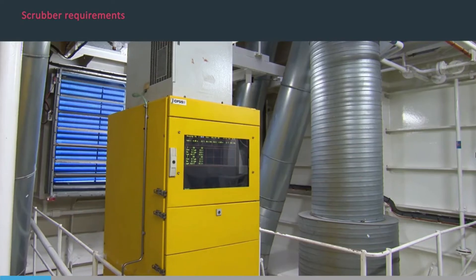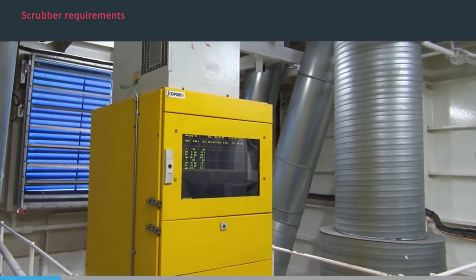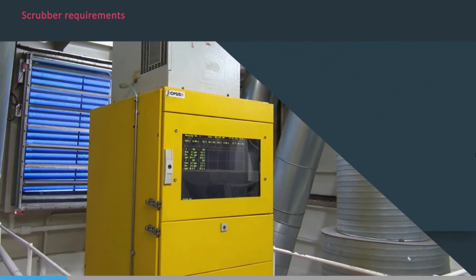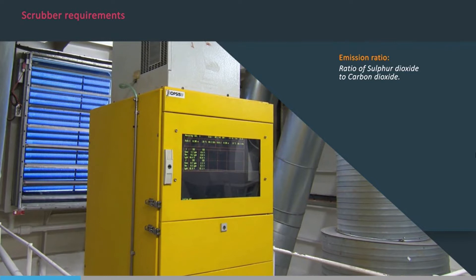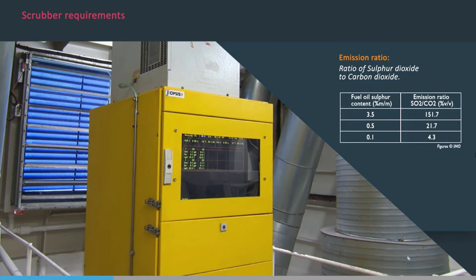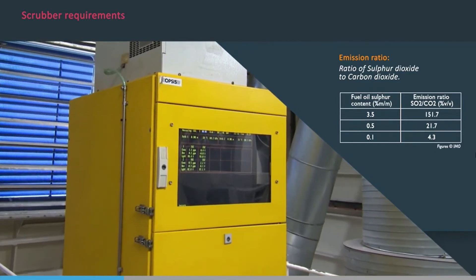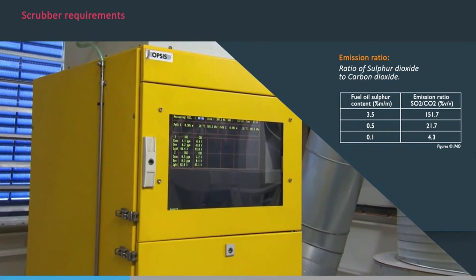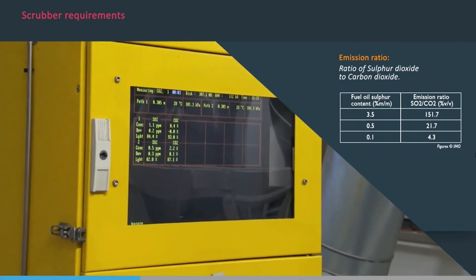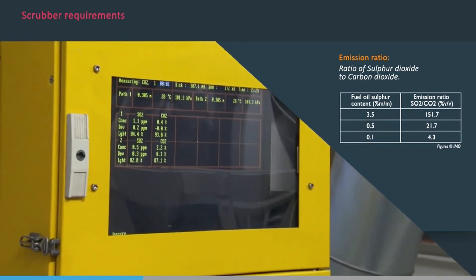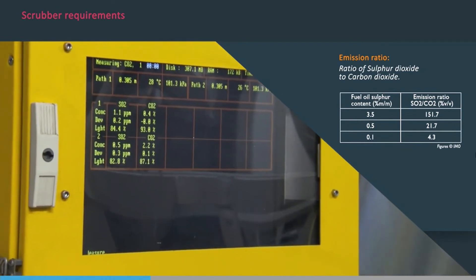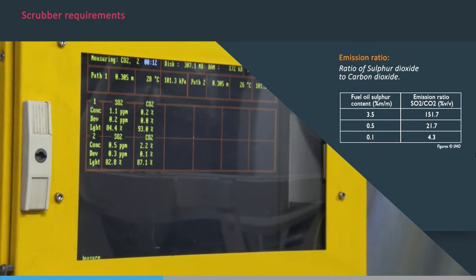To give a meaningful measure of the amount of sulphur oxides present, the IMO use the emission ratio, which is the ratio of sulphur dioxide to carbon dioxide in the exhaust gas, by volume. These emission ratios are known for fuels of different sulphur content, and the sulphur dioxide and carbon dioxide present in the exhaust stream can be measured. It can therefore be established if the scrubber has reduced the emission ratio of a high sulphur fuel to the equivalent of that of a low sulphur fuel, required for the area where the ship is located.